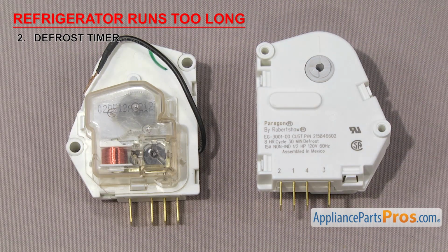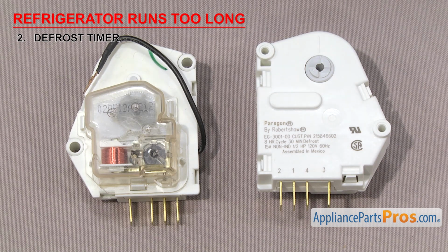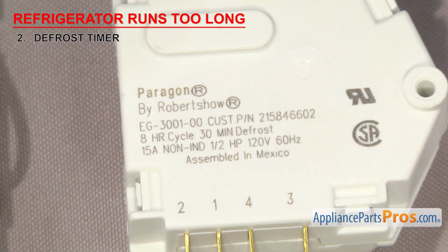Now we need to look at the defrost timer. It controls the defrost cycle of the refrigerator. The defrost timer is made up of a motor, gears, and contacts. It switches the refrigerator between the cooling and defrost cycles and helps keep the evaporator free of ice buildup. They have a set number of hours for cooling and minutes of defrost. As an example, this one will run for 8 hours and defrost for 30 minutes.